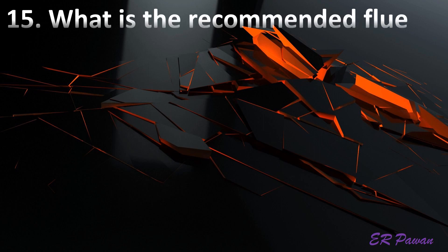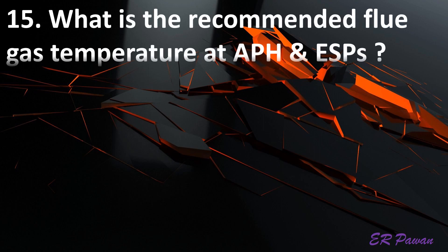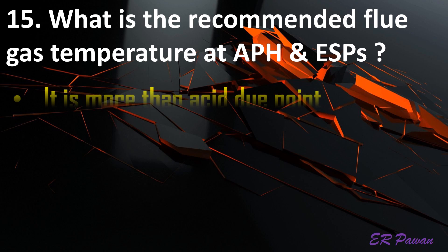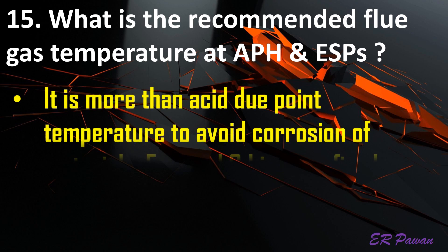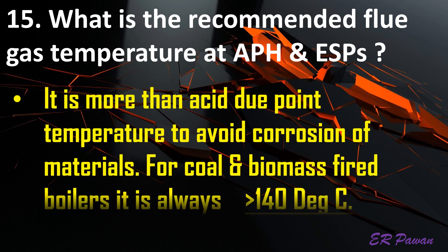Question 15: What is the recommended flue gas temperature at air preheaters and electrostatic precipitators? It should be more than the acid dew point temperature to avoid corrosion of materials. For coal and biomass fired boilers, it is always greater than 140 degrees Celsius.